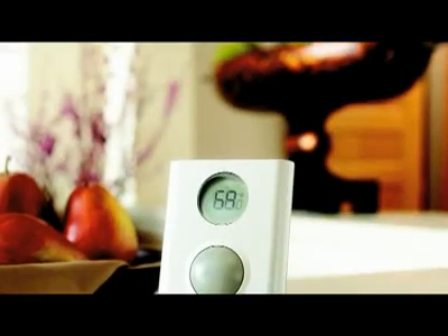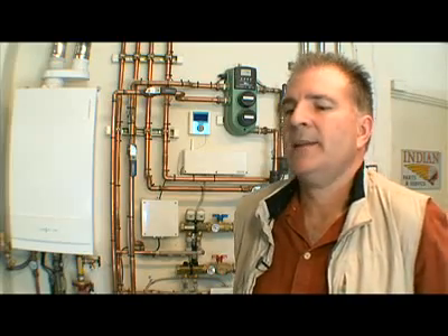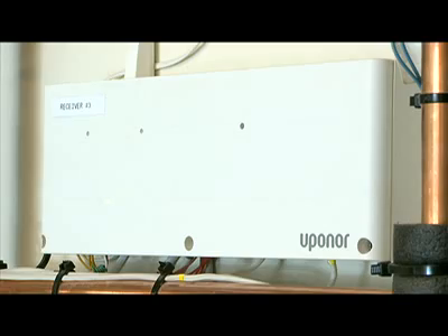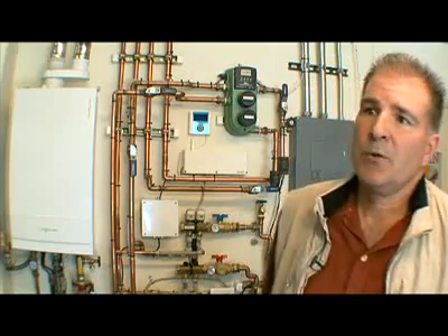The system is simple and innovative and, as it turns out, a problem solver on the job site. What we find and underestimate as we top out our homes installing radiant heating is the amount of time it takes to wire — even on the rough-in part, that's when the wiring gets done. What the wireless provides is we don't have to pull any wire from the thermostat location back to the mechanical room where the receiver is located. We still have to pull wire from the receiver to the remote actuator location, but significantly less wiring. And at the price of copper, that's a significant savings.